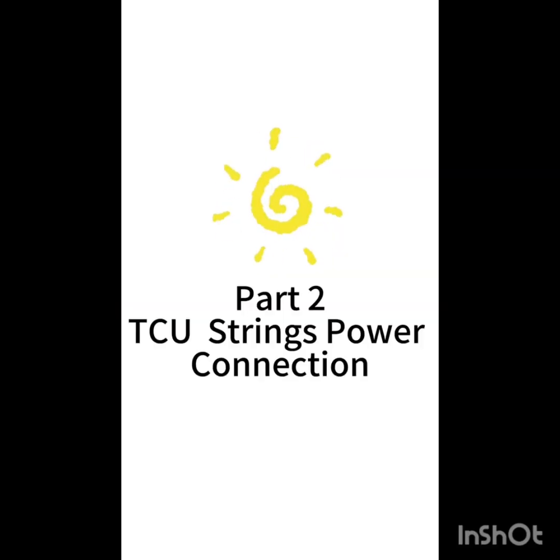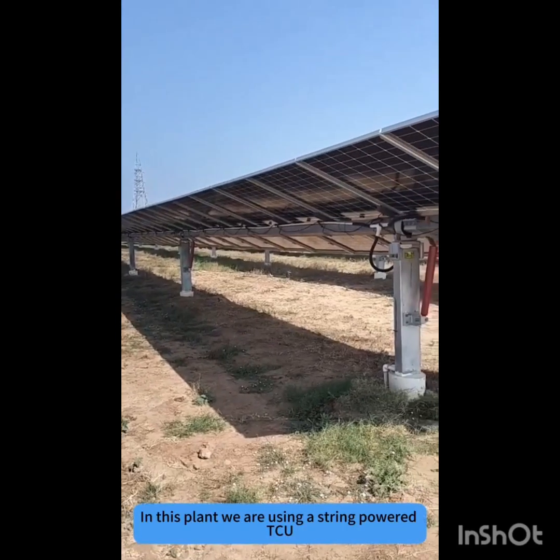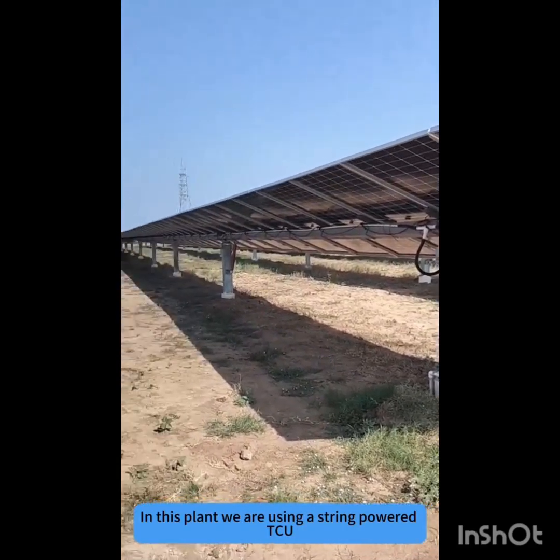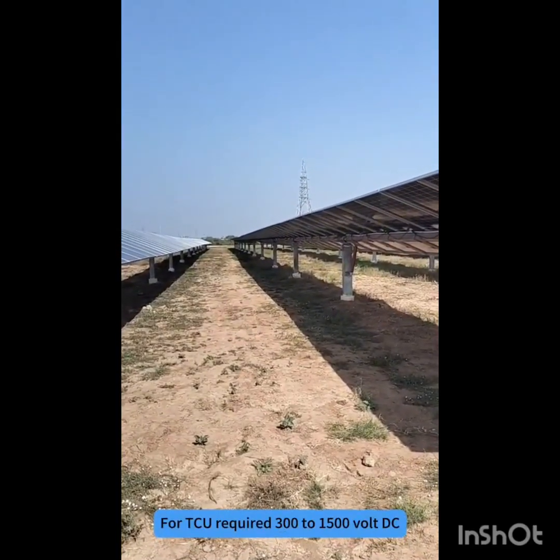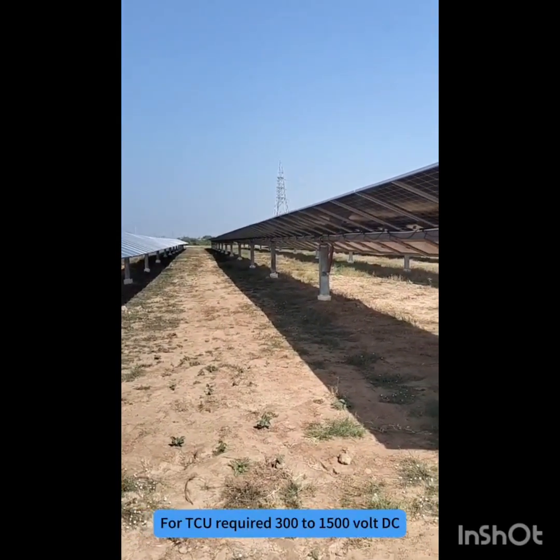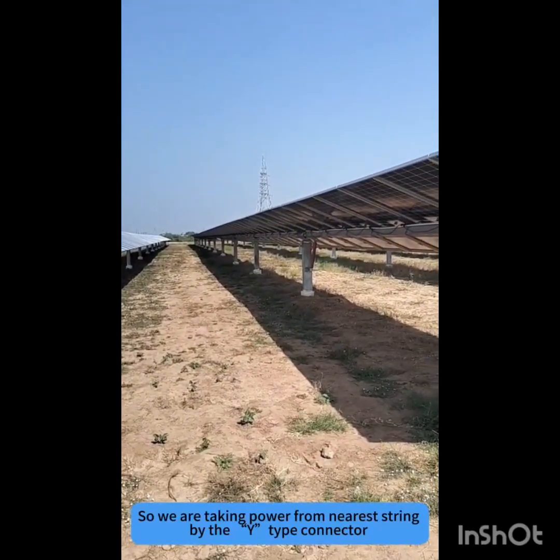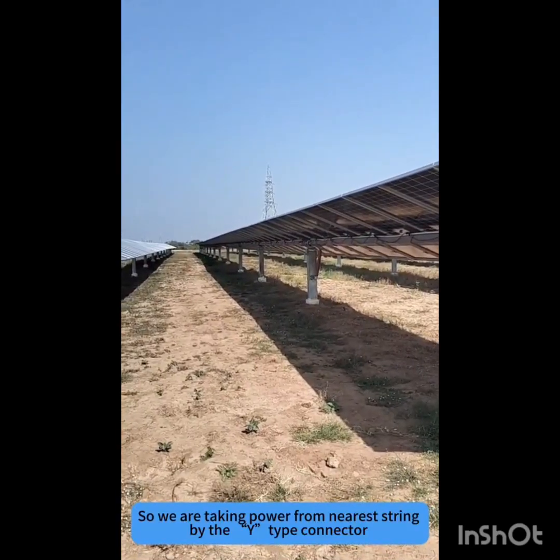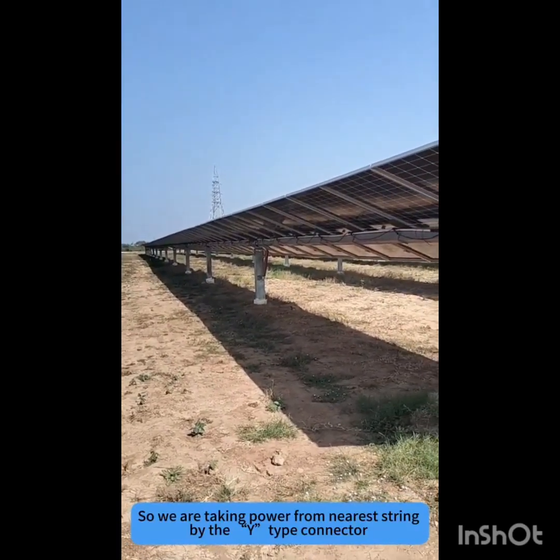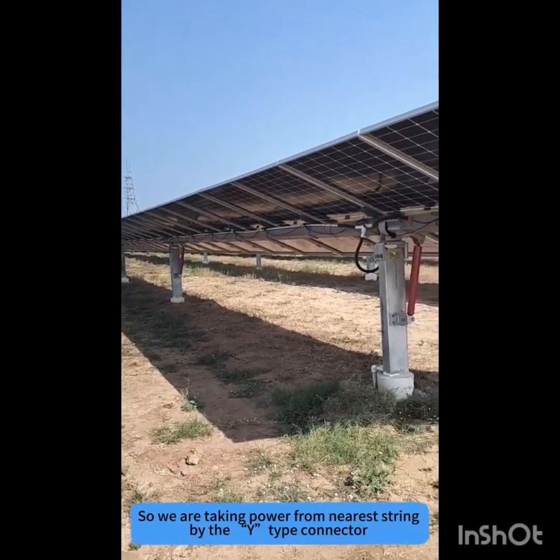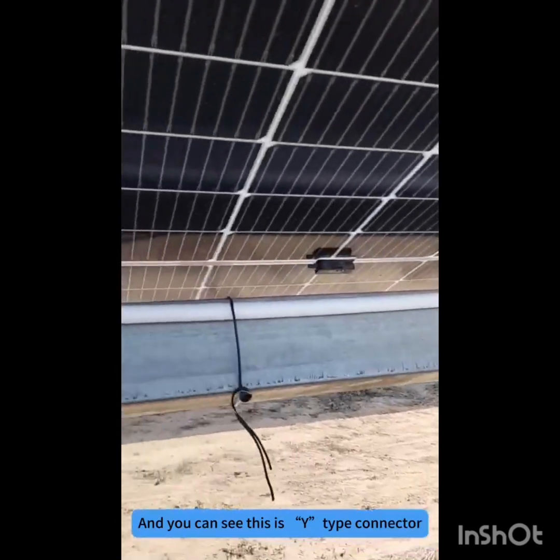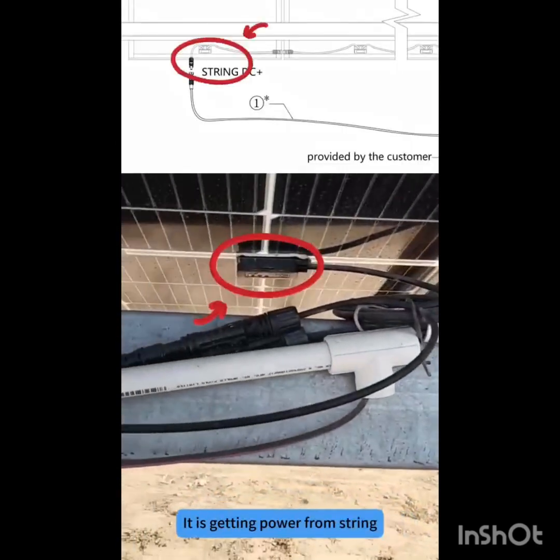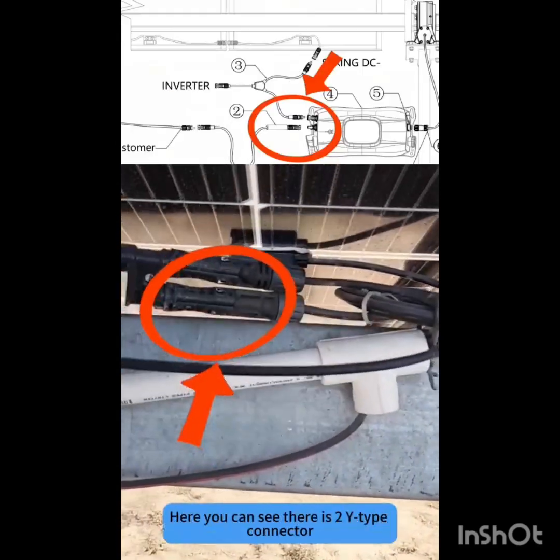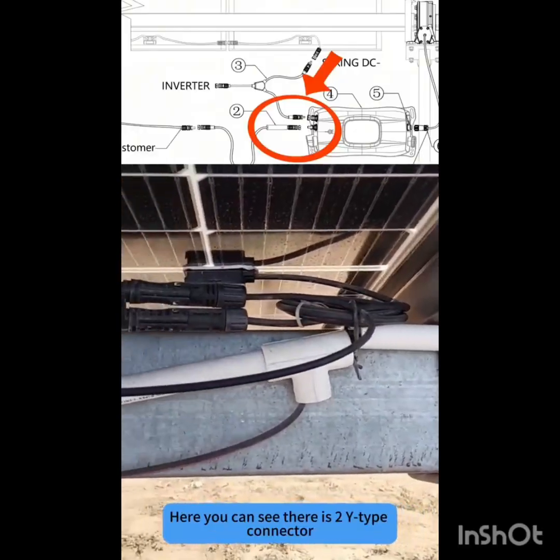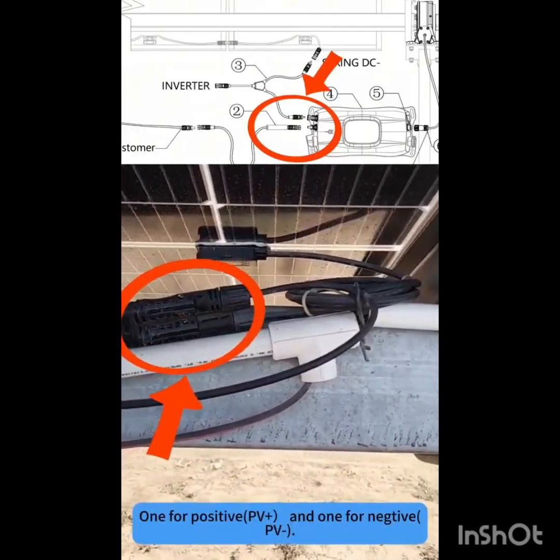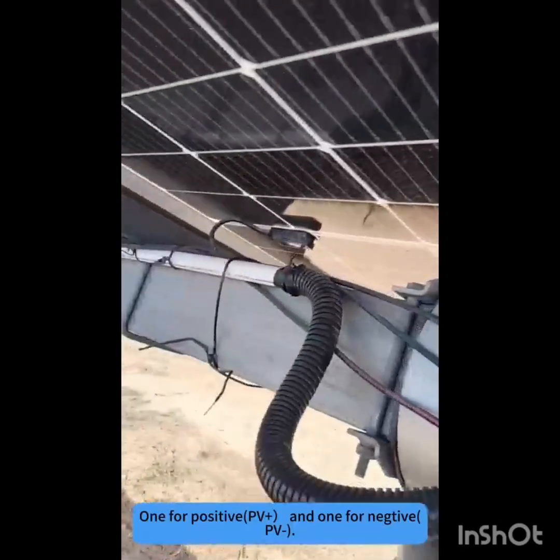Part 2. TCU string power connection. In this plant we are using string power for the TCU. For the TCU it is required 300 to 1500 volt DC. So we are taking power from the nearest string by the Y type connector, and you can see this is the Y type connector. It is taking the power from the string. Here you can see there are 2 Y type connectors. One is for positive and one is for negative.